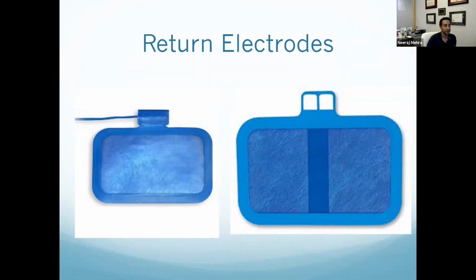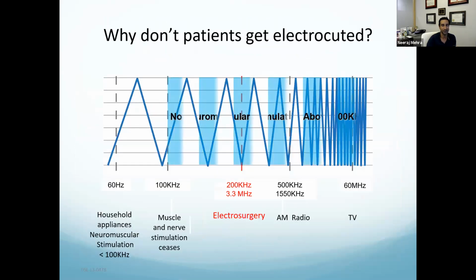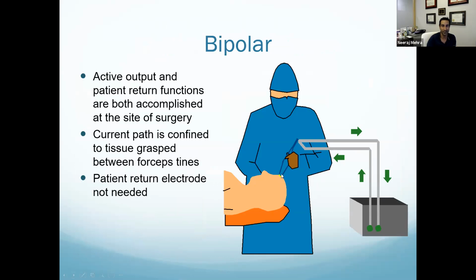So the nurses will put it on, but you don't actually need it because the patient is not part of the circuit in this case. The return electrode is only needed if you're using monopolar energy, where the patient is part of the circuit. If you're using bipolar energy, you don't need a return electrode because the return electrode is in the instrument itself. So it goes one way, comes back the other way. And it's not part of this talk, but if you get into some of the advanced energy sources, things like the LigaSure or the BiClamp or other similar instruments, those are all forms of bipolar energy. Again, those are electrosurgical energy, but they don't have a return electrode because the patient is not involved in the circuit.